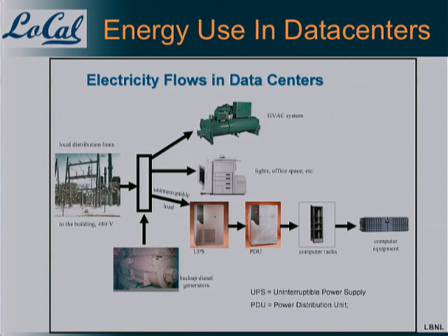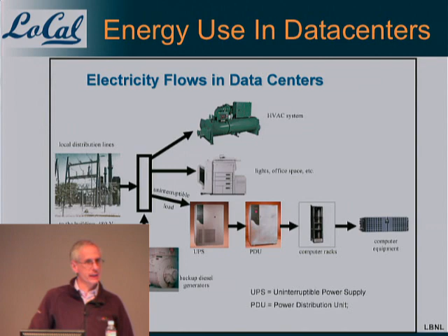They often have a rather complex, albeit local, distribution system that provides redundant power, converts the power at various levels in order to deliver the necessary power to where it's needed, to the racks of computers. A common factor used in describing these things is power utilization efficiency, or PUE, which is intended to capture: if I were to just power the computer equipment, I would have a certain amount of power consumption in my building. How much extra overhead is associated with the distribution system itself and the necessity of cooling both the distribution system and the computers? PUE is typically, for most modern data centers, in the range of 2 to 3. What that means is that all the infrastructure in support of the computers uses 2 to 3 times as much power as the IT equipment itself.